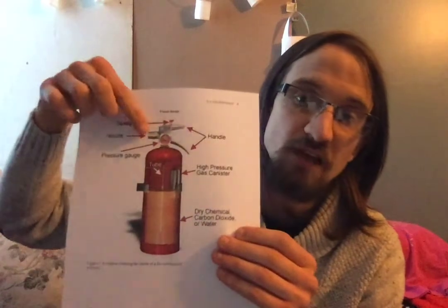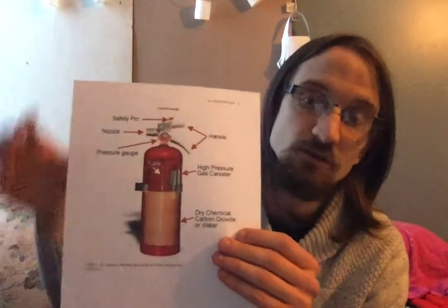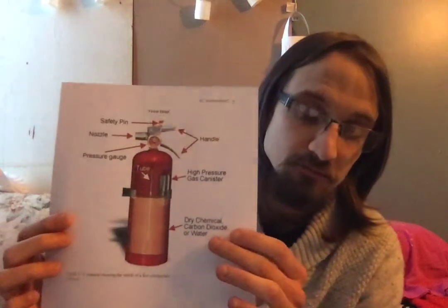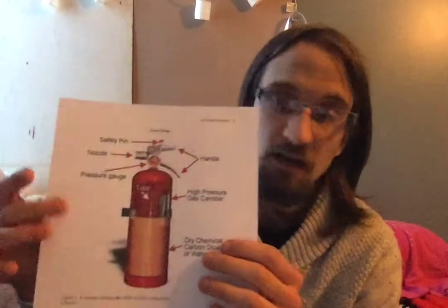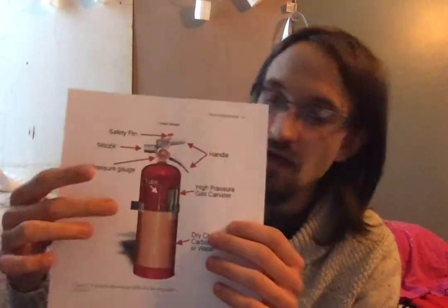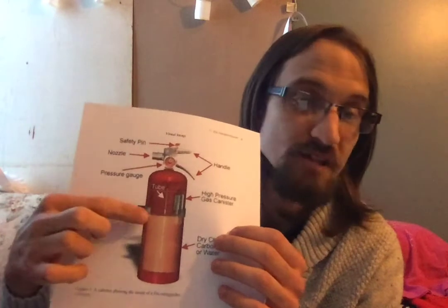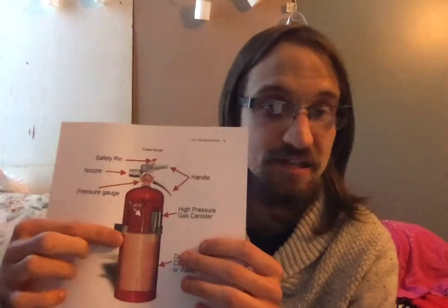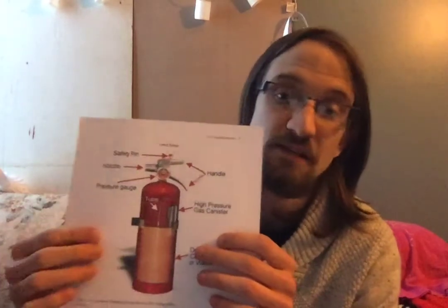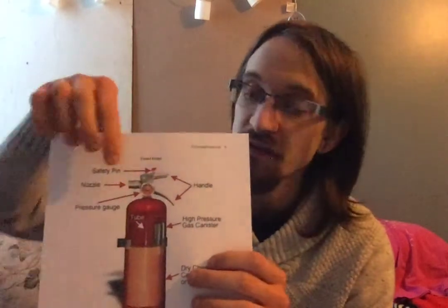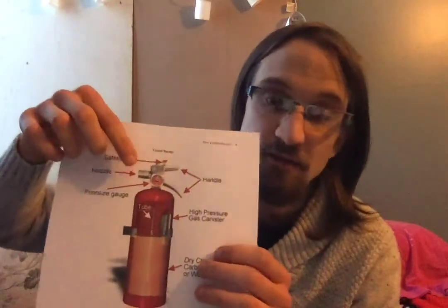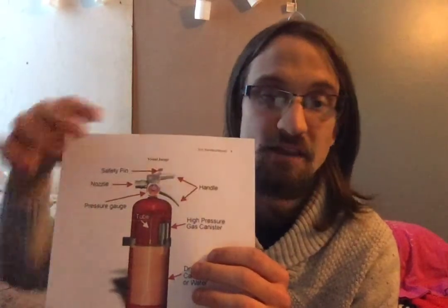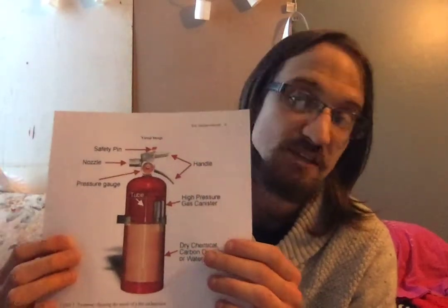There is also a pressure gauge, and that is used to determine when your fire extinguisher is going to be empty, so you know when to get it refilled. There are a couple other parts that aren't shown here, and that is a label, which would be on the outside of the fire extinguisher, and that would show what type of fire extinguisher it is, what classes of fires it can put out, and the capacity of the container. The other thing that's not pictured is an inspection label, and that would be attached at the handle up at the top here, and that would provide a record of past inspections as well as letting you know when the next inspection is due.